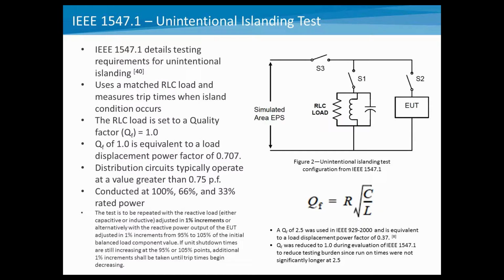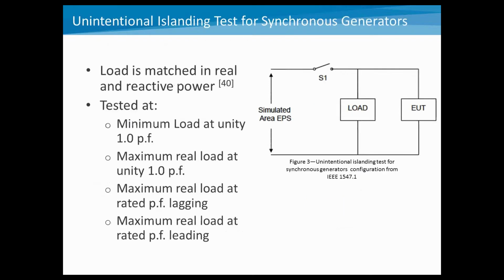In older tests, like in 929, we were using a quality factor of 2.5. Based on a lot of testing we did in the early 90s, we came to the conclusion that we were seeing very similar results using a quality factor of 1, and that was much easier to actually set up and run for that particular test. So that's why the standard now has a Q of 1.